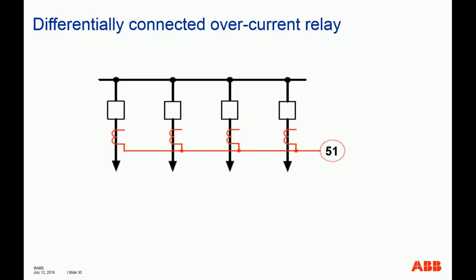Also, the major drawback of this type of connection is, obviously, there's no internal algorithm, as I mentioned. So there's no way this relay can deal with, for example, CT saturation. Modern bus differential relays all have some type of saturation detection algorithm, or a dual slope, or sometimes a triple slope to deal with CT saturation. But this simple type of connection wouldn't have that arsenal in place to deal with that type of complexity.